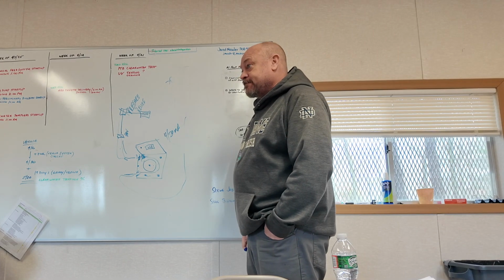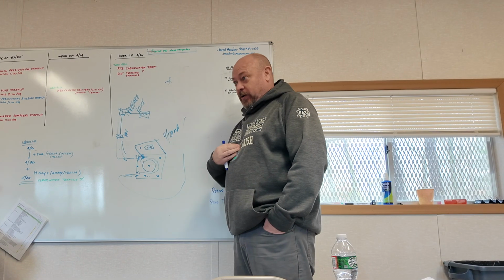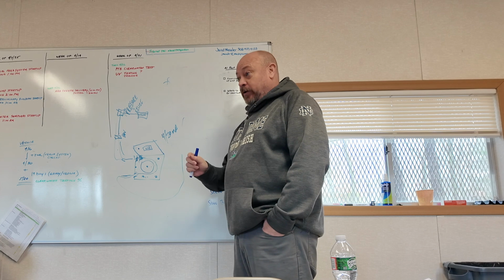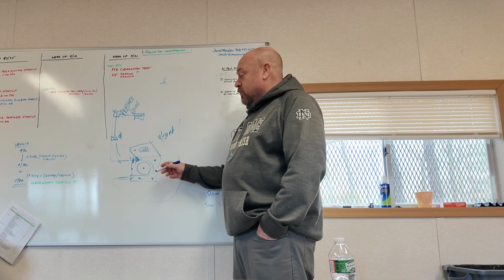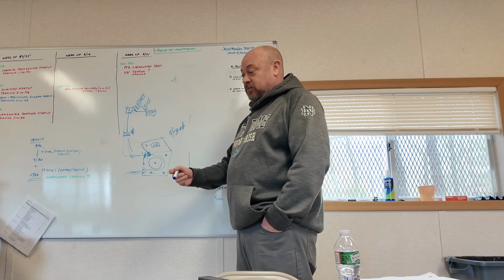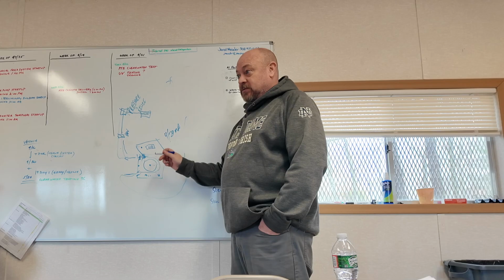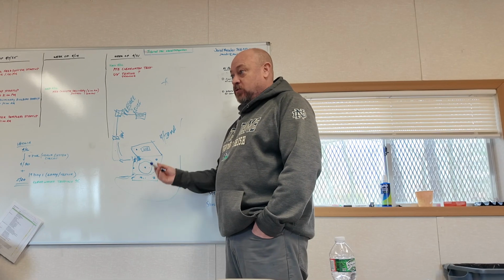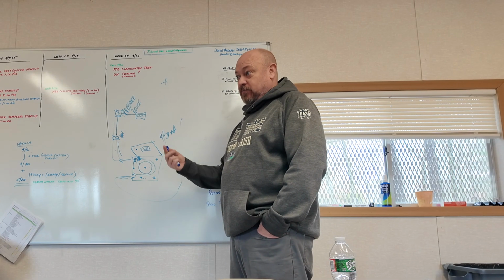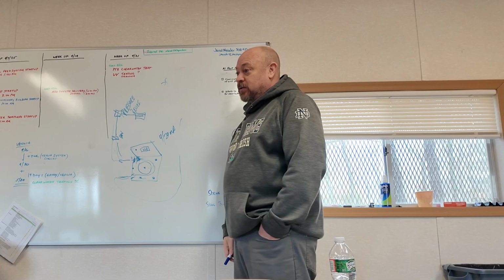Does the shaft need to be lithium grease or anything like that? I would recommend putting grease on that shaft. Food grade grease, yeah, because you're dealing with chemicals. And even though you're on a wastewater side of things, trying to find a compatible grease with hypochlorite and caustic, usually food grade is a lot more compatible than trying to find something else. A little bit more expensive, but it'll last a little longer.